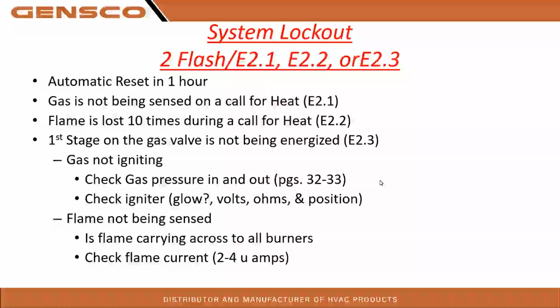Okay, so we're going to look at a system lockout at 2 flash. It's going to be an automatic reset in 1 hour. So basically, gas is not being sensed on the call for heat. So it's a 2.1 error on the S series furnace. Flame is lost 10 times during call for heat. That would be a 3.2, or a 2.2, excuse me, on the S series furnace. First stage gas valve is not being energized, 2.3 on an S series furnace.